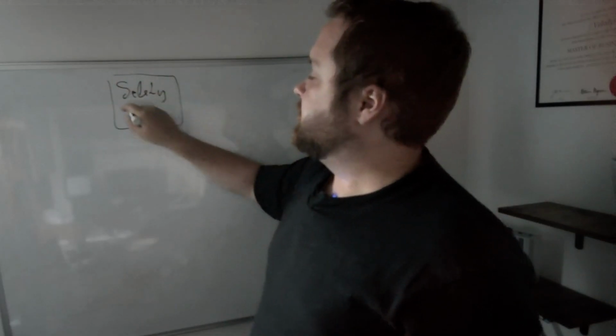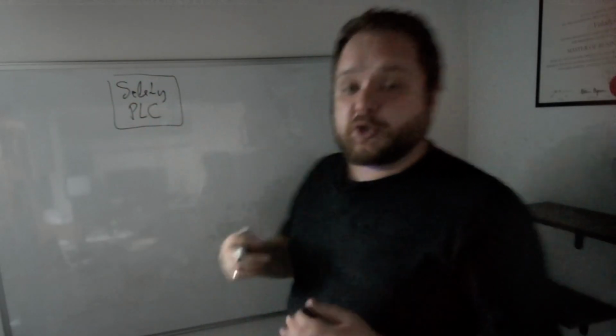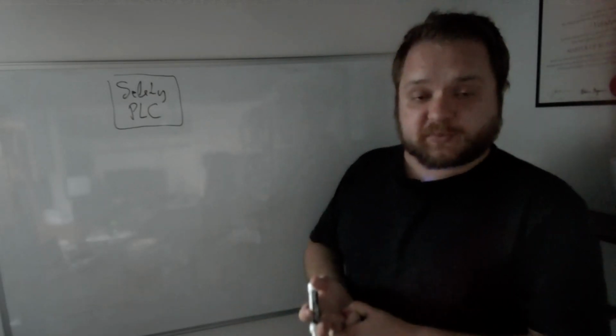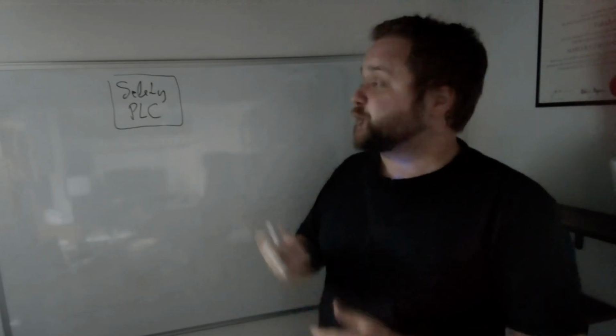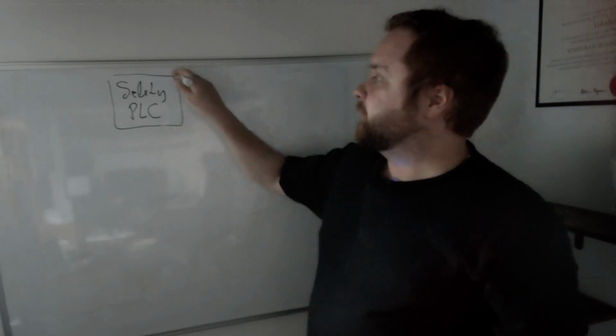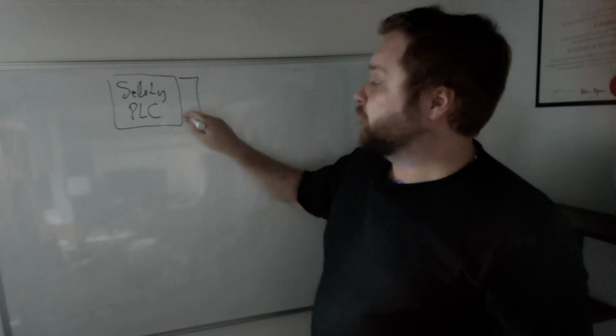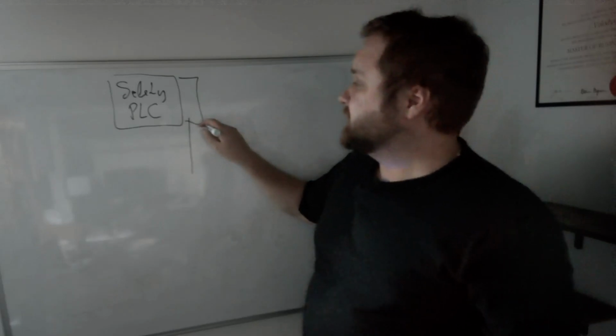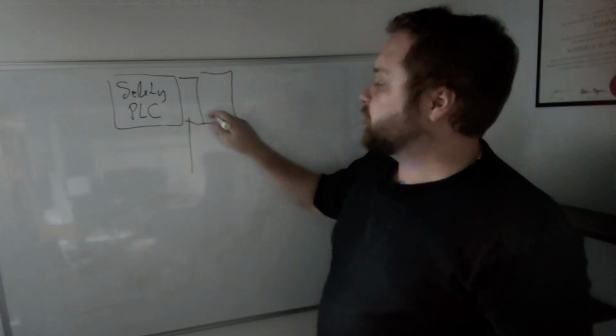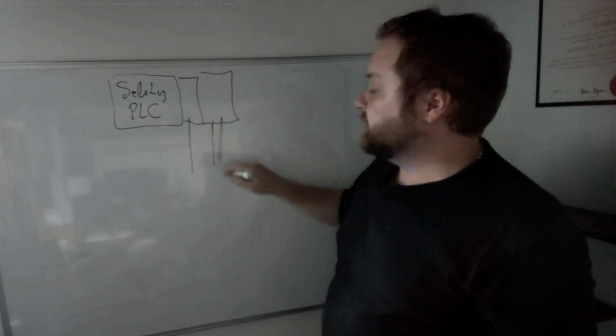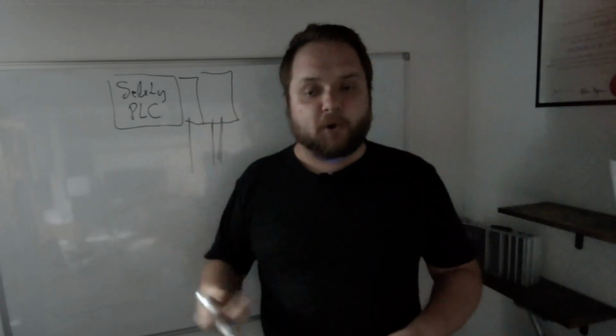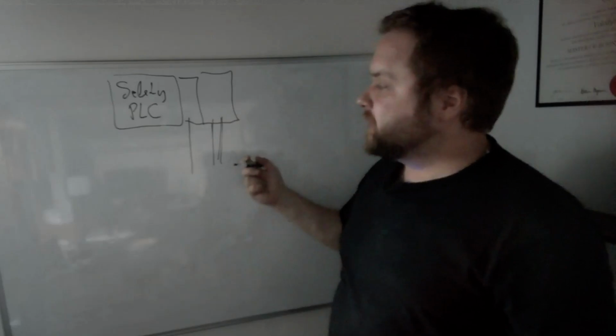So the other question that gets brought up is around other safety components. If you've worked in industrial automation long enough, you will know that there are what are called safety PLCs. Safety rated PLCs are usually going to be, number one, more expensive. They're going to be dual redundant, so they are also required to have, again, let's say, an I/O card of a normal PLC where you have a single channel. Safety rated PLCs are going to feature cards with dual channel safety, and then dual channel both inputs and outputs rated for the safety application.